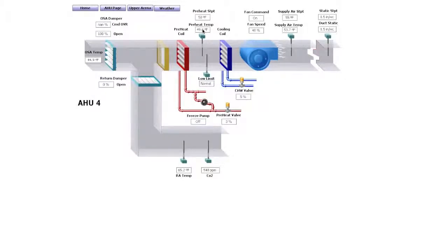And again, this is March, and there's a demand for some cooling in the space. But because it's cold outside, they're taking advantage of free cooling. They've got the outside air damper open, bringing in fresh outside air and blowing it into the office for comfort cooling. And this is a great graphical look for this individual office unit.